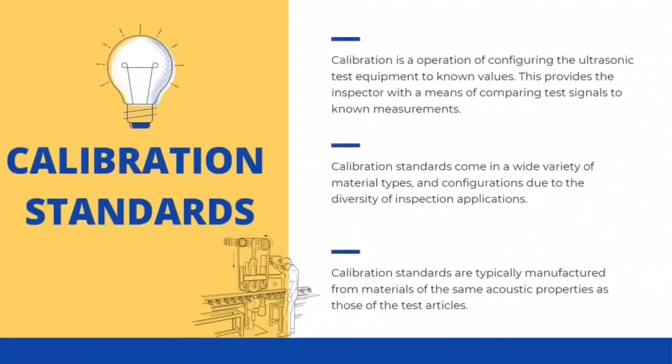The last basic component is the calibration standard. Calibration is an operation of setting up the ultrasonic test equipment to a known value. This provides the inspector with a means of comparing the test signal to a known measurement.